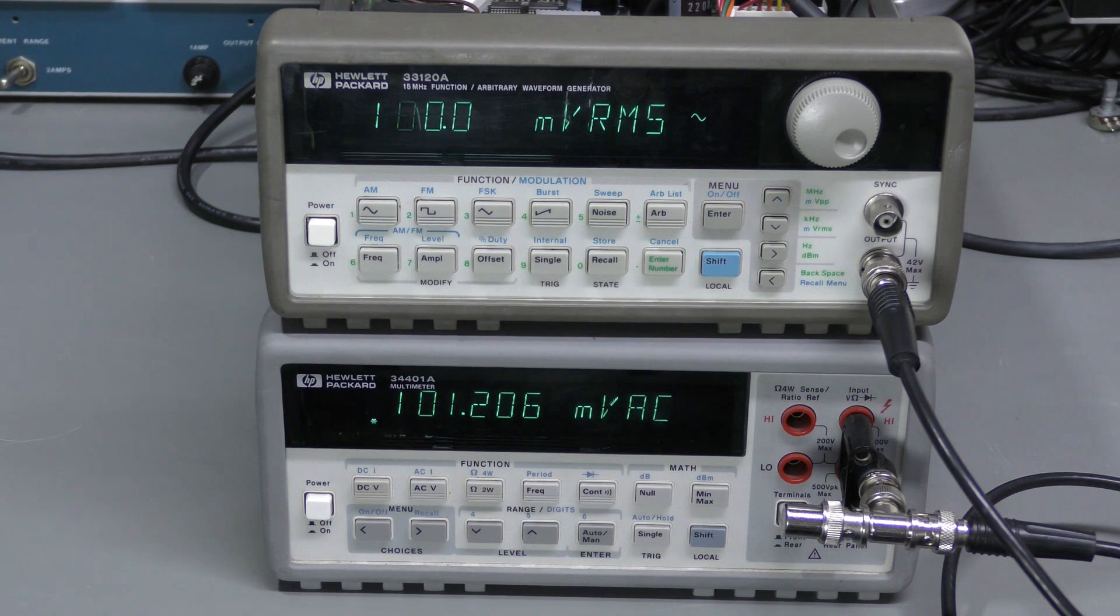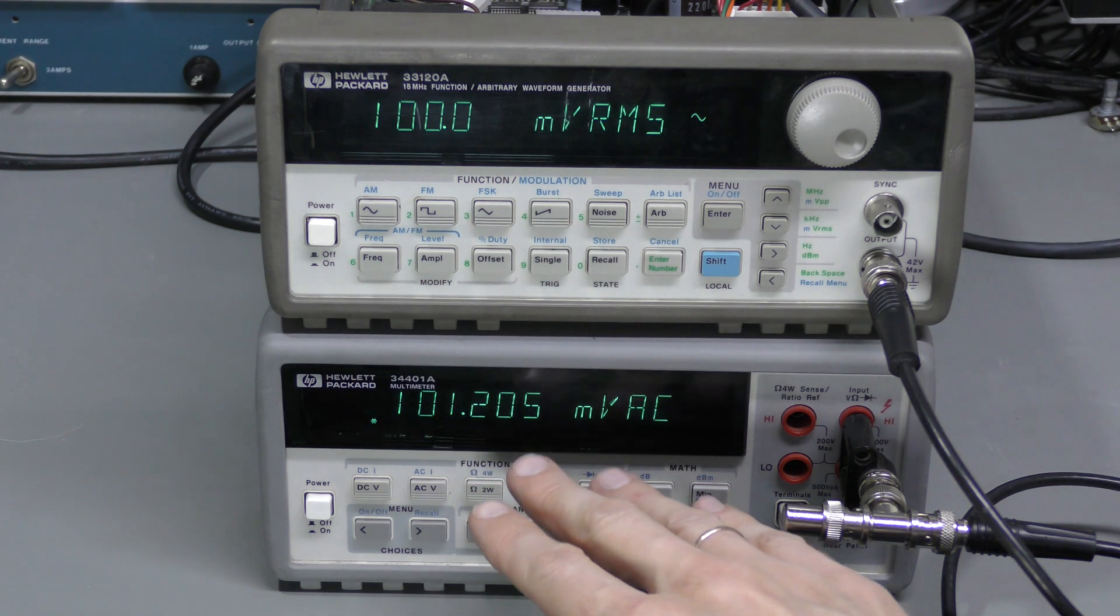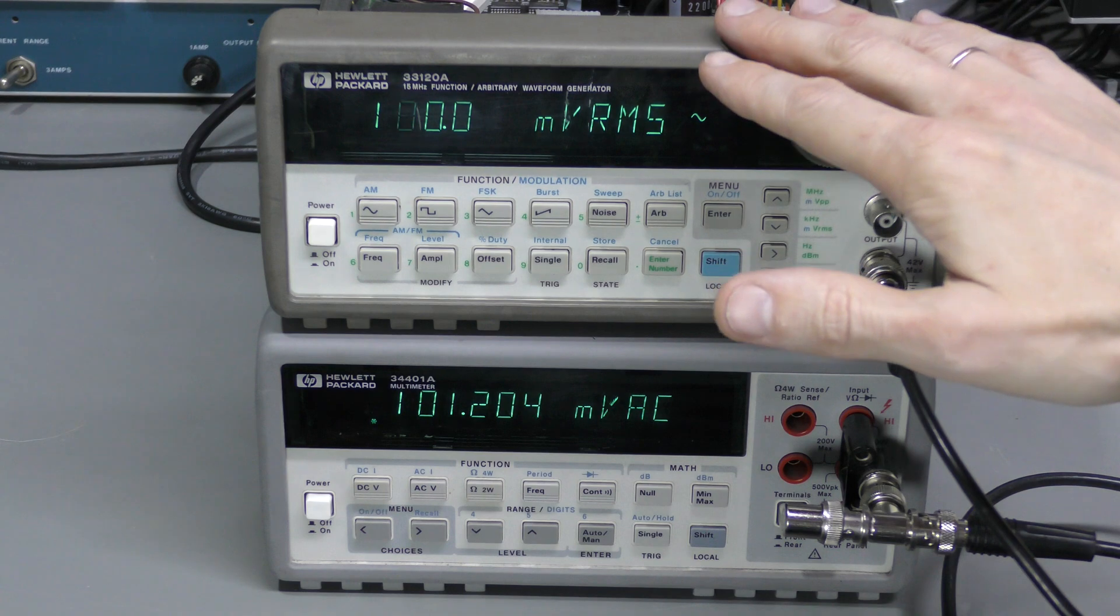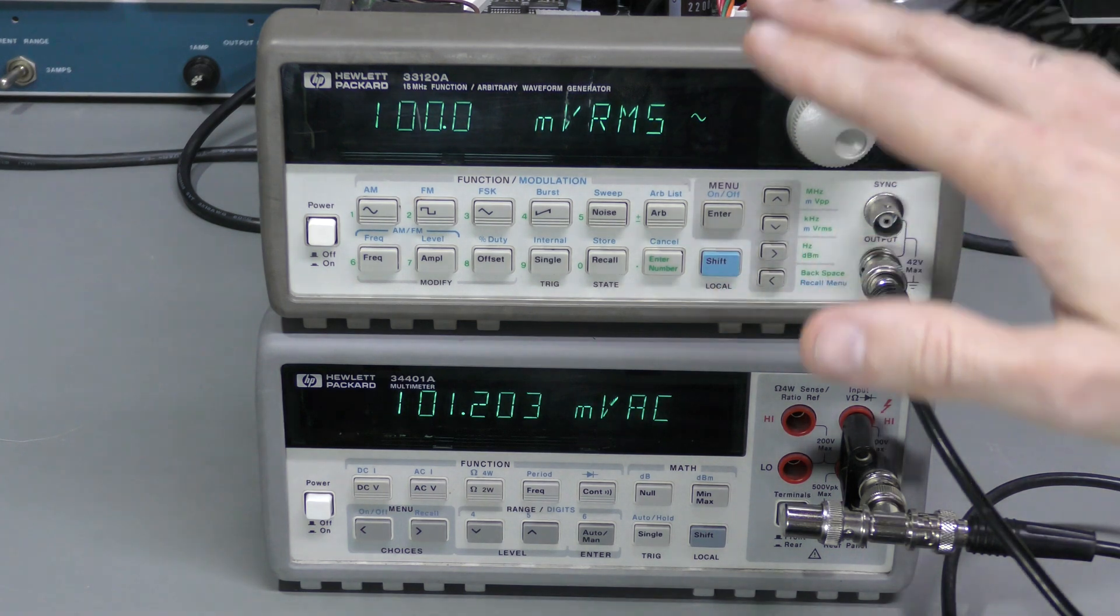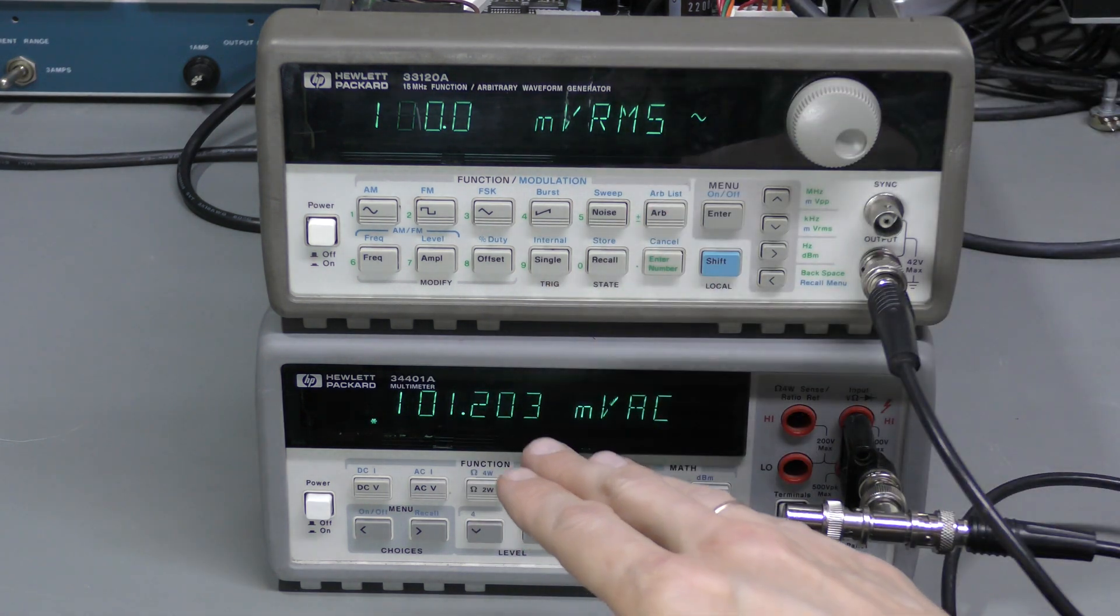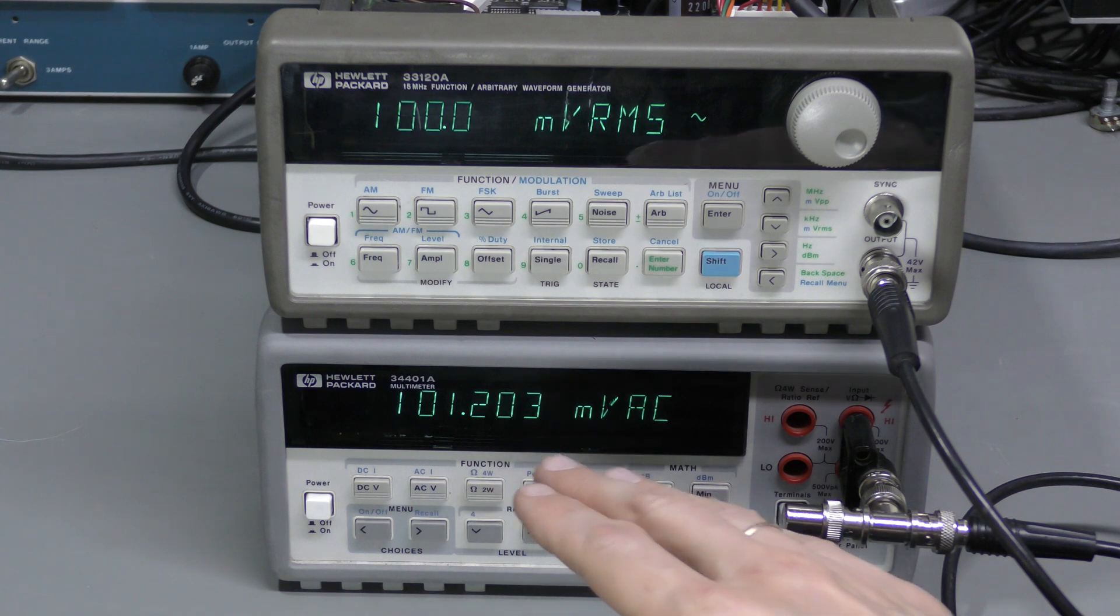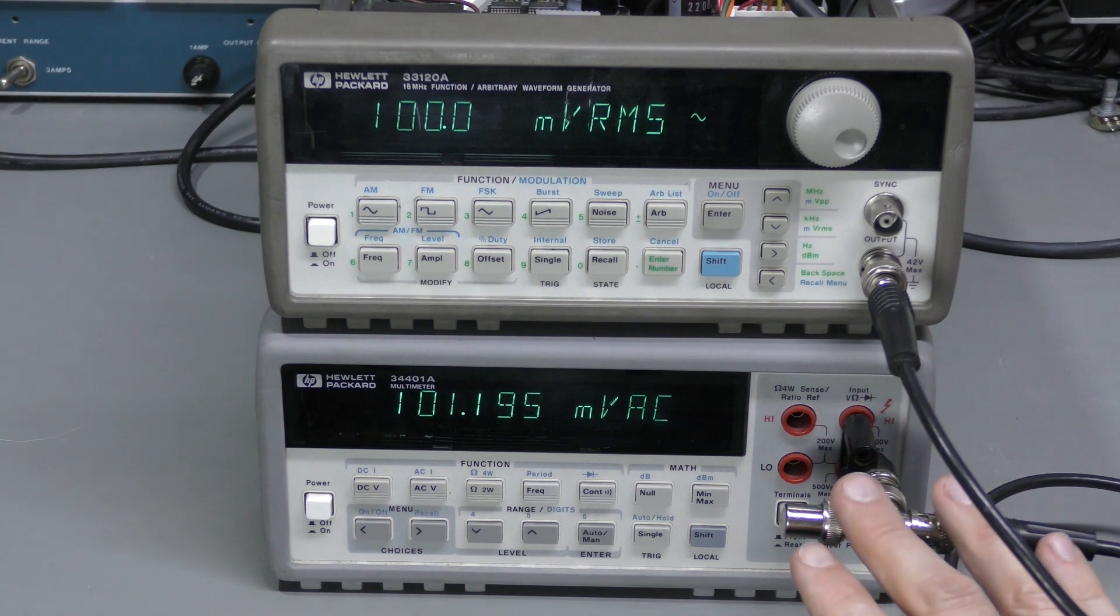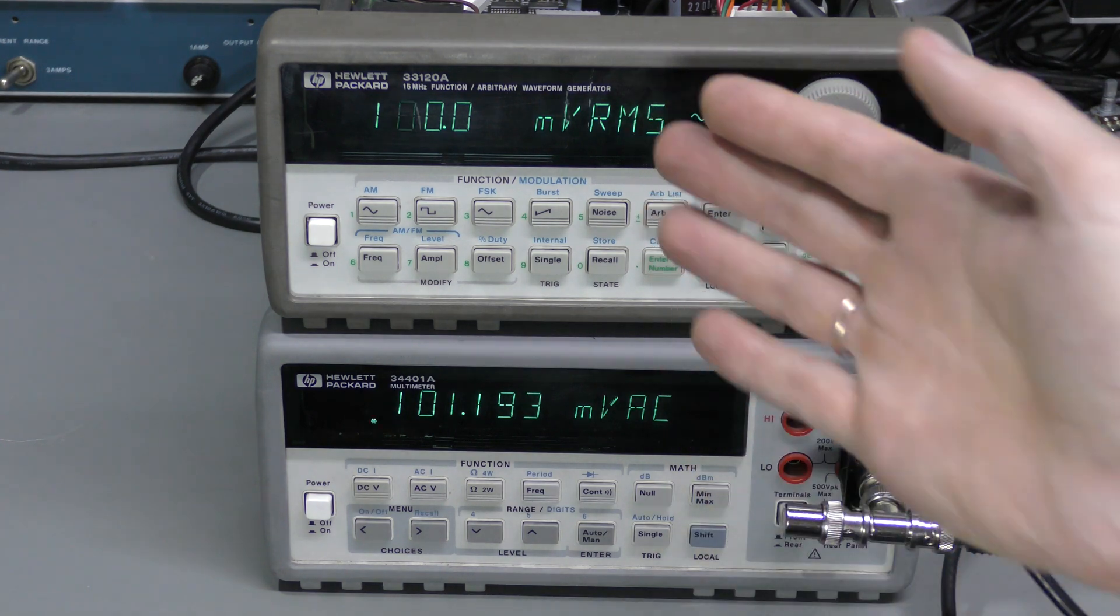It seems like I was right. I followed the calibration procedure in the service manual using this 6.5 digit multimeter. I did not record this, it's just a long and boring procedure. Nothing complicated, just follow the manual. The generator puts out particular amplitudes, and you're supposed to enter back what you read on the multimeter. Some steps are done with 50 ohm termination, and some steps with high Z.